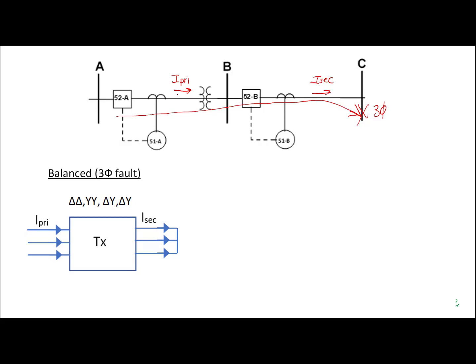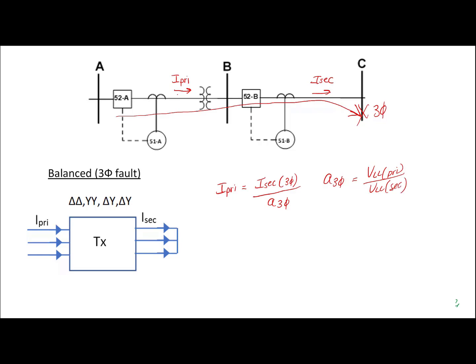Since this fault is balanced, we can calculate that I_primary is simply going to be I_secondary — which is the three-phase faulted current — divided by a_3φ. So that will be the primary current. We know that a_3φ from previous courses is our V_line-to-line primary over V_line-to-line secondary. This allows us to calculate what the primary fault current will be when the fault is on the secondary and it's a three-phase bolted fault.